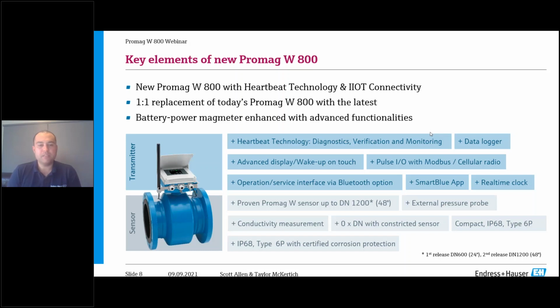Some of the key aspects the flow meter will have: heartbeat technology, which we'll cover off, with the major function being around verification—the ability to health check and verify the meter in situ. It'll come with a data logger, anywhere between 10,000 to 50,000 data points. The TFT display has an energy saving, battery saving function where it goes to sleep, and to wake it up you just hold your finger on it.